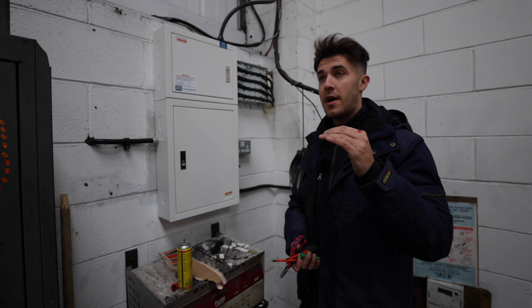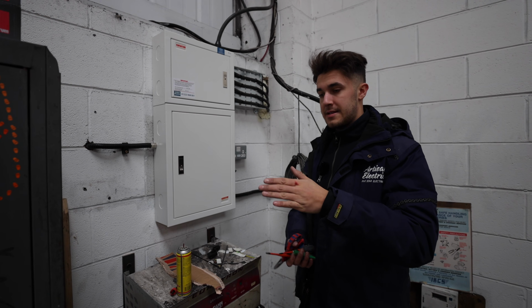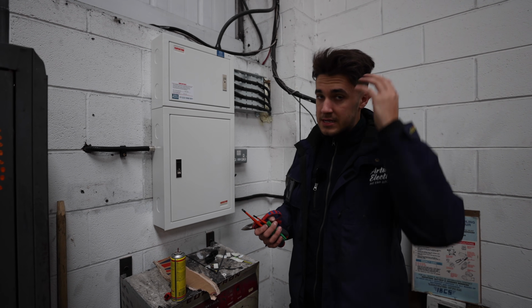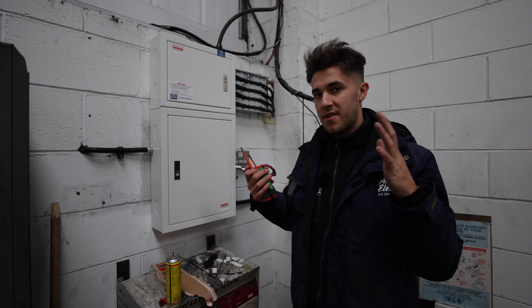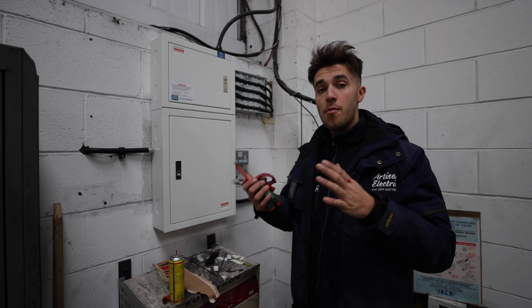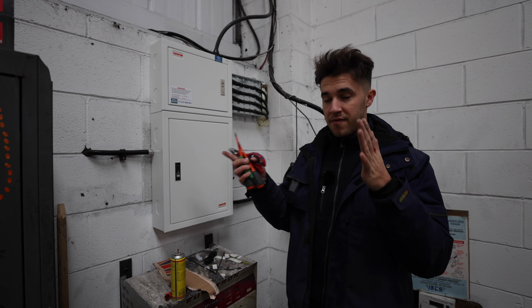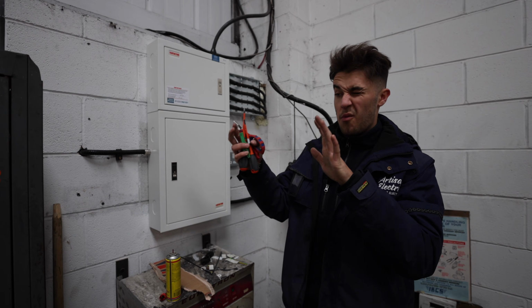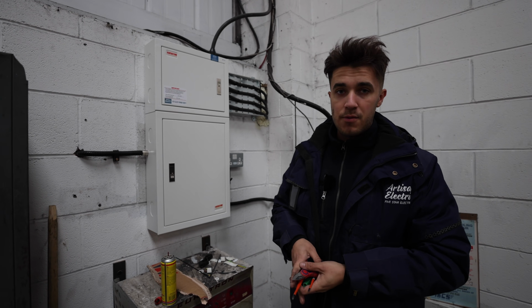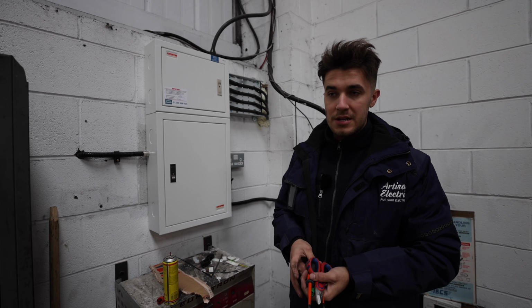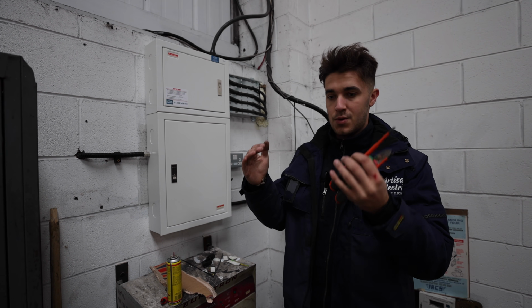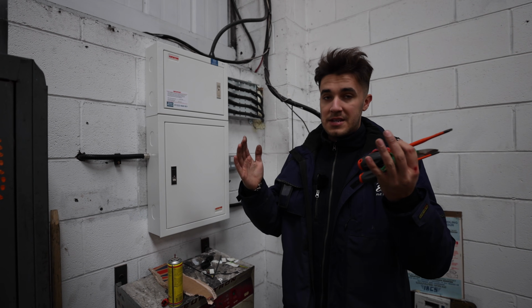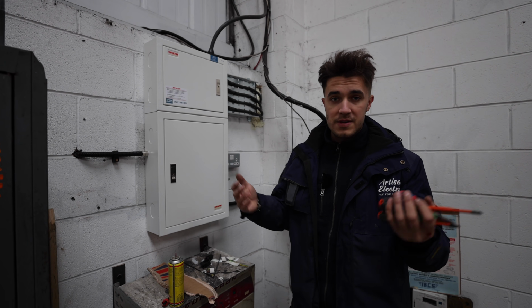Two things. When I got the on-site guide out to explain cable tray, I said, oh yeah, this is the measurement - there isn't actually a set measurement for cable trays, so I'm sorry if I misled you there. I go by the trunking measurement as a rough guide, I look at that and think, well, roughly what size is it? The proper way to do cable tray is quite complicated - you need to look at the manufacturer's instructions and get the right spacing for whatever cable you've got on there so it's not going to sag.